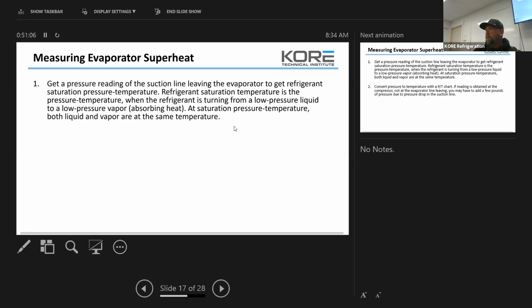What you're going to do is look at what your gauges are telling you, and then take your clamp temperature. That's one temperature. And then you're going to take your pressure and convert it to temperature. And you should see the differential there. So the difference in the temperature is your superheat. If it's too low, you're still too saturated. If you have it running like a 2 degree superheat or a 4 degree superheat, depending on the system, you might be not boiling off enough inside the evaporator, and you're sending too much liquid back to the compressor.